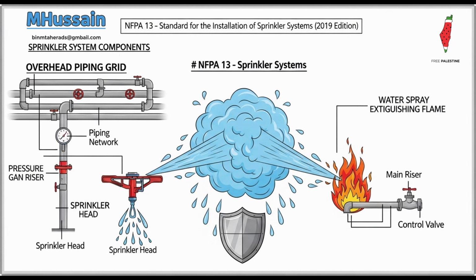Right. And that difference between grounding and bonding is subtle, but absolutely crucial. You cannot use the piping as the main path to ground the building's electrical service; that could introduce massive, dangerous electrical surges onto the pipe during a fault. But you must bond the piping to the electrical grid. This prevents damage from smaller stray currents, maybe from equipment faults, or even lightning nearby, that could cause corrosion or degrade the pipe integrity over time. So understanding that distinction between prohibited use as a grounding electrode and mandated bonding for electrical safety, well, that's essential for maintaining both fire safety integrity and the long-term lifespan of your fire suppression system. Something to definitely think about the next time you inspect a project site.